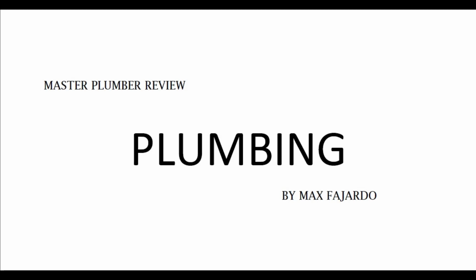3. The soil branch. The soil branch is a soil pipe installed horizontally with lateral or vertical connections that receive the discharge of water closets with or without additional plumbing fixtures. General conditions in installing soil branch. 1. The soil branch, being concealed in floors, partitions, or lowered ceiling, should be accessibly provided with a sufficient number of cleanouts.